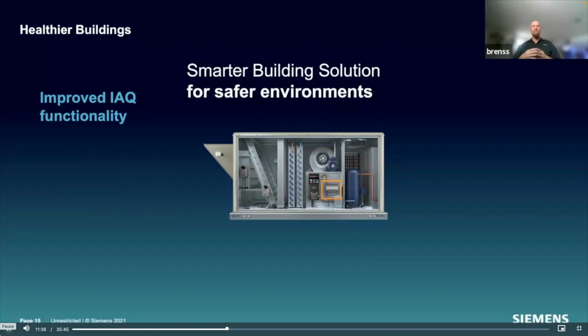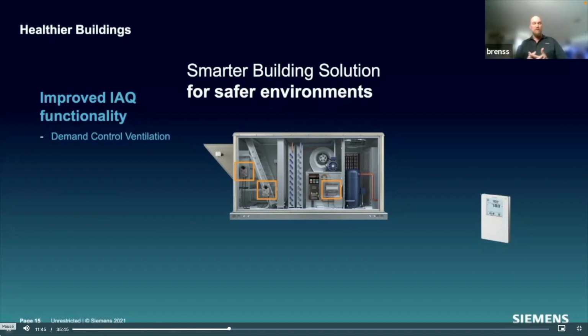What we've done is we've improved the indoor air quality function. Demand control ventilation is built already into the controller. Depending on when you hook up your room unit, it will know by reading your indoor air quality and will adjust your dampers for you to try to maintain fresh air. We also have a patent pending purge function, which allows us to purge the air completely in a zone. Lots of our partners are using this, advertising with this. And just recently, we had a report that one of our country clubs that are advertising our purge function, their membership has gone up 30% this year alone, only because people want to be in a safer environment.